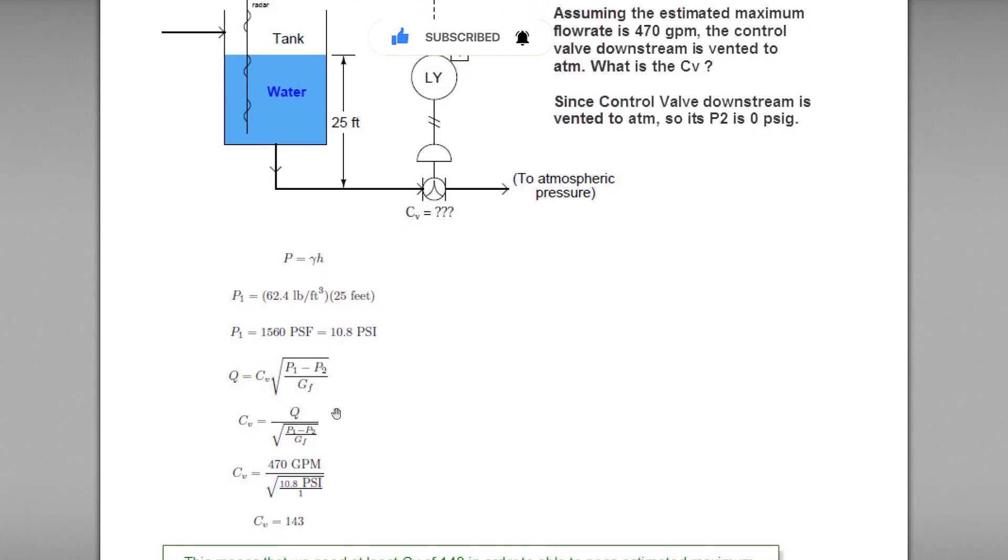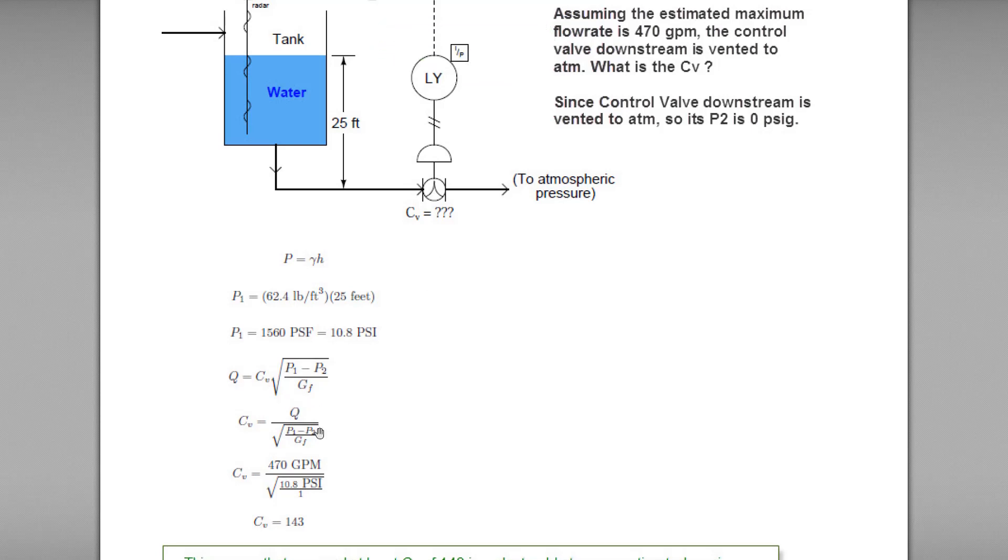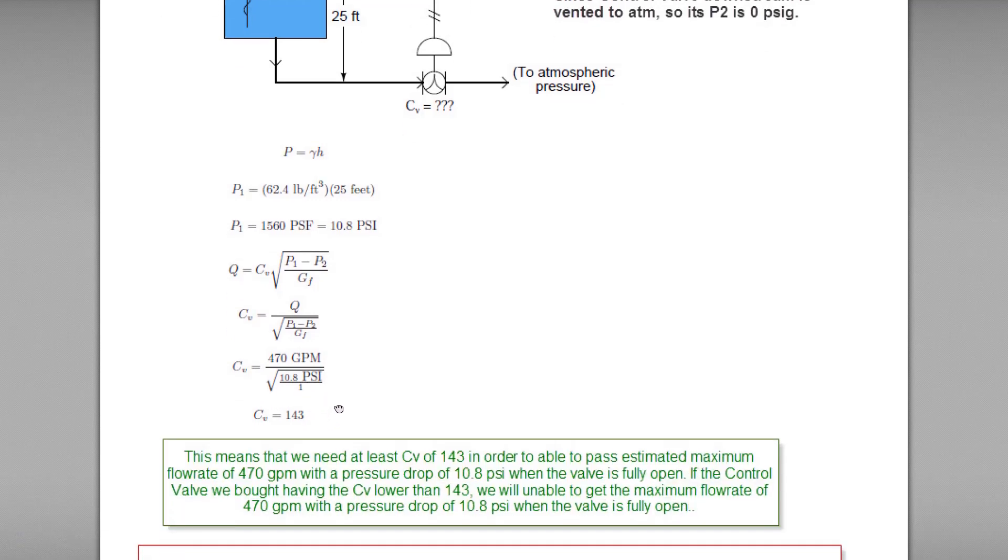So this is the formula for volumetric flow rate. You can put in the value that you have. The Q volumetric flow rate is 470 gallons per minute. Then the P1 upstream pressure is 10.8. The downstream pressure is 0. As I mentioned the P2 is 0. The specific gravity for water is 1. So the CV will be 143.